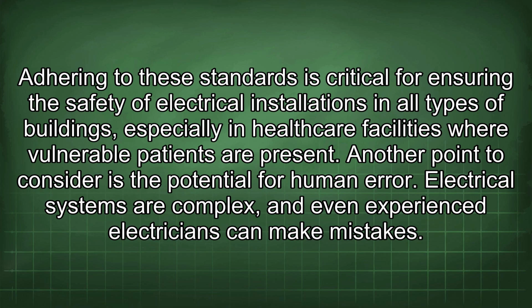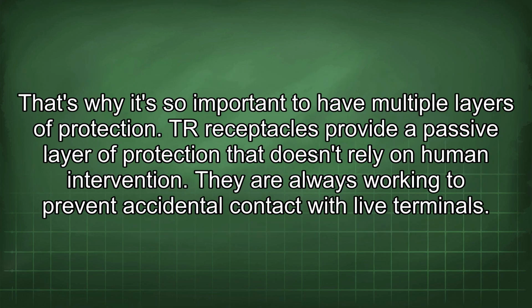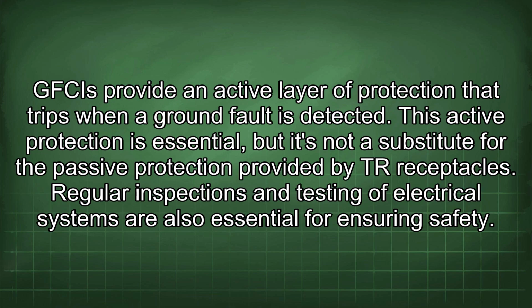Another point to consider is the potential for human error. Electrical systems are complex, and even experienced electricians can make mistakes. That's why it's so important to have multiple layers of protection. TR receptacles provide a passive layer of protection that doesn't rely on human intervention. They are always working to prevent accidental contact with live terminals. GFCIs provide an active layer of protection that trips when a ground fault is detected. This active protection is essential, but it's not a substitute for the passive protection provided by TR receptacles.